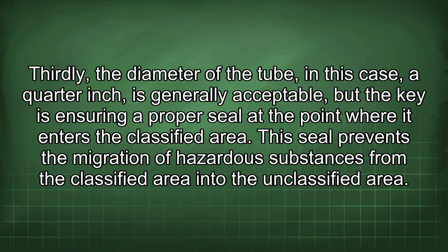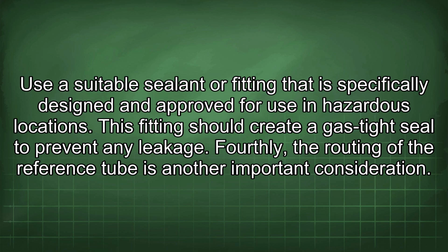Thirdly, the diameter of the tube, in this case a quarter-inch, is generally acceptable, but the key is ensuring a proper seal at the point where it enters the classified area. This seal prevents the migration of hazardous substances from the classified area into the unclassified area. Use a suitable sealant or fitting that is specifically designed and approved for use in hazardous locations. This fitting should create a gas-tight seal to prevent any leakage.